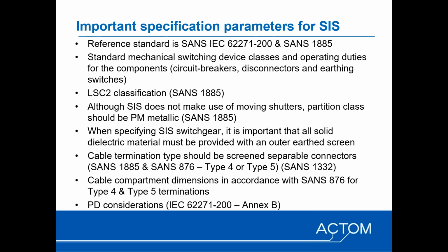SANS 876, which covers the insulation requirements for conductors and medium voltage enclosures, as well as requirements for cable terminations, defines 5 different types of cable terminations. Type 1 is a bare uninsulated termination, type 2 a shrouded or covered termination, type 3 an unscreened separable connector, and type 4 a screen separable connector with an outer cone type bushing. That is currently the more common variation of a screen separable connector in South Africa, but it's also important to note that type 5 terminations are covered in SANS 876, and that is the inner cone or plug-in termination, particularly, for example, at some of the higher voltages such as 36 kV and where higher currents are involved.